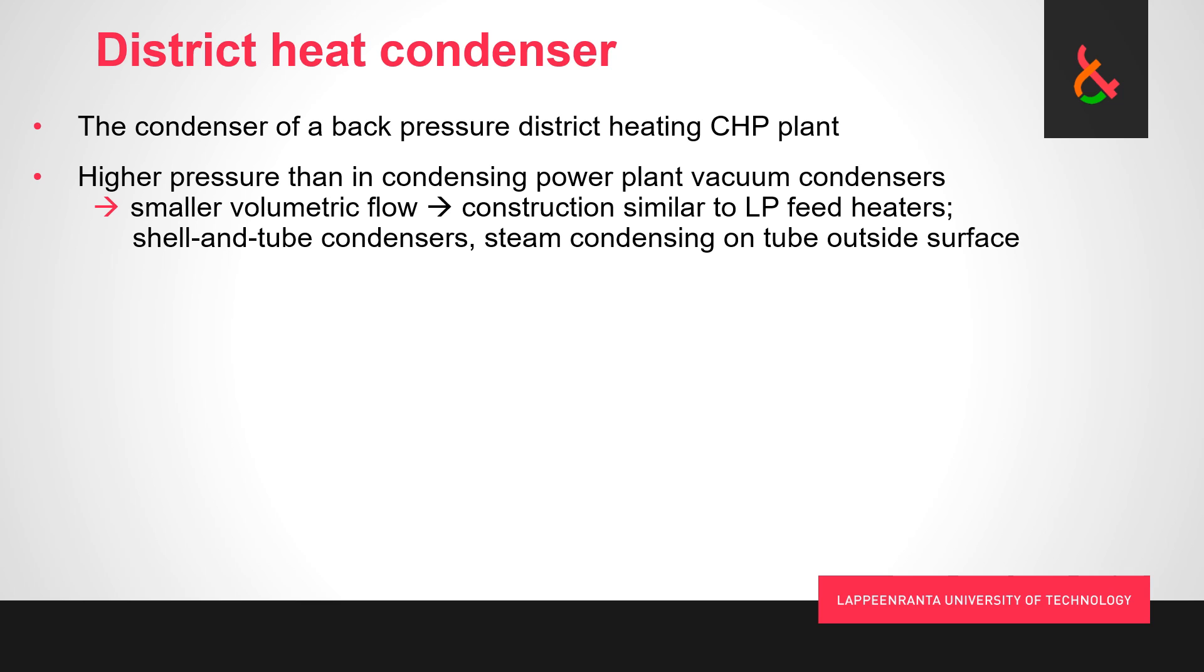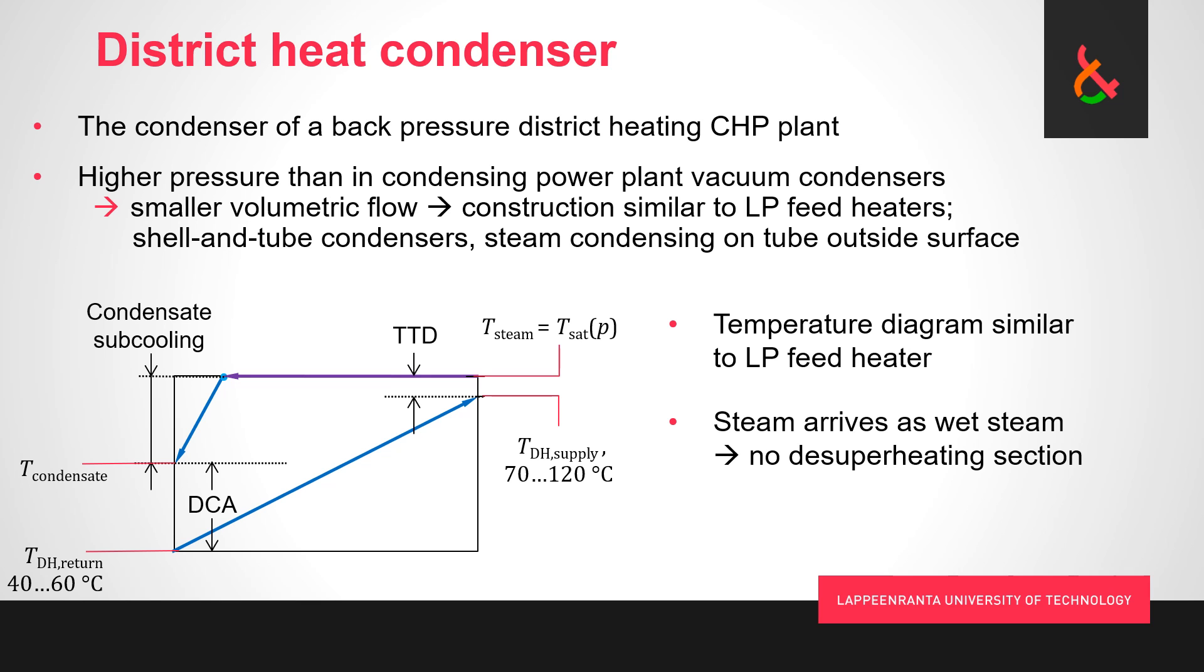We always want to draw the temperature diagram, so this is more or less how it looks. Same idea as with a condensing power plant vacuum condenser. We always get steam in wet steam state, so no desuperheating. Fairly low TTDs—we're talking about maybe 2, 3, 4 degrees Celsius typically.